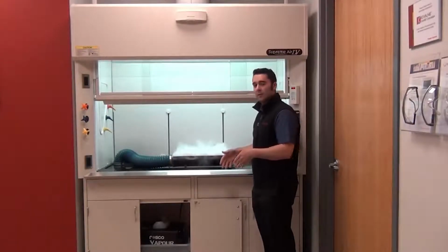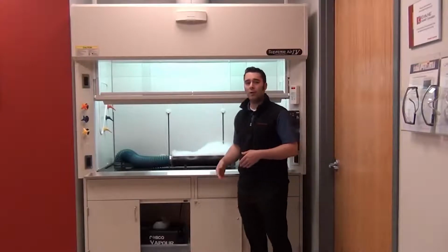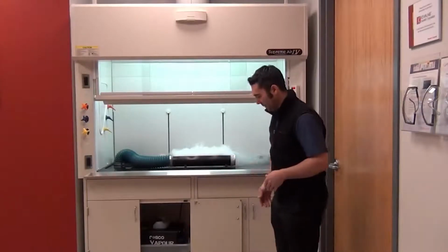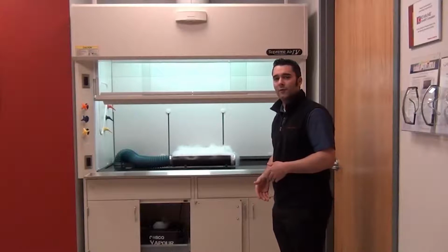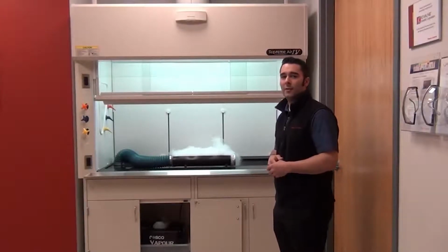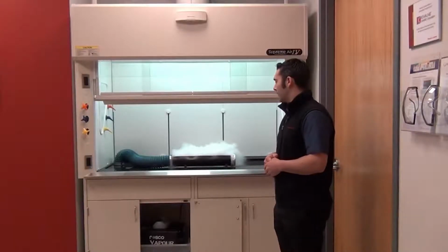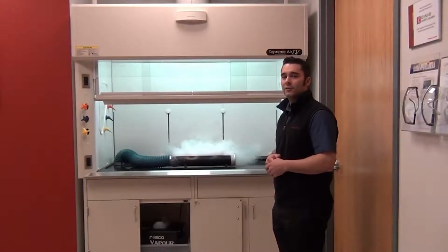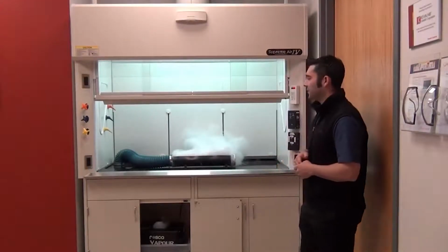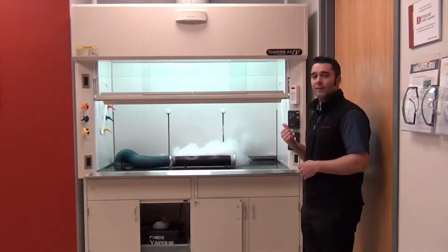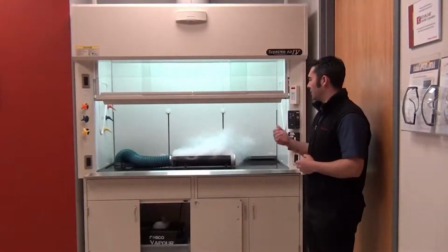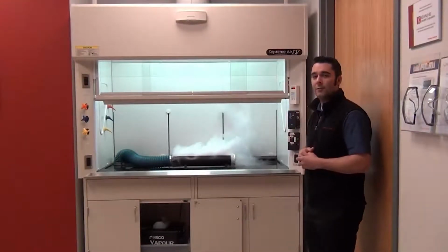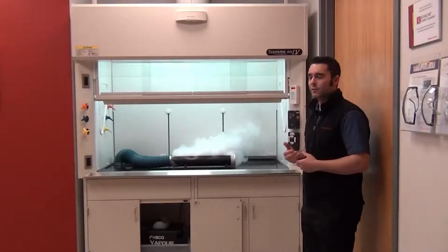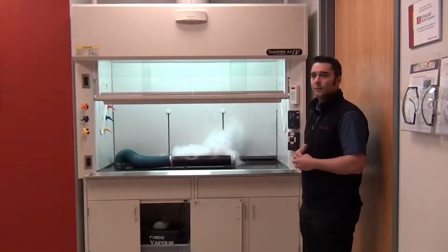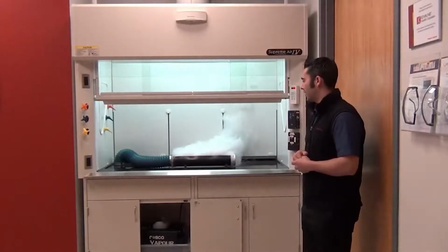I can also trigger the sensitivity to make it work when somebody is only 2 feet or 3 feet away from the fume hood. It will still go into setback mode to guarantee that I'm not wasting energy or having nuisance setbacks. So right now this fume hood is running at 60 feet per minute versus 100 feet per minute. You can see there is still no loss of containment because of the stability of the Phoenix Controls product and the pressure independence that we have in our product.